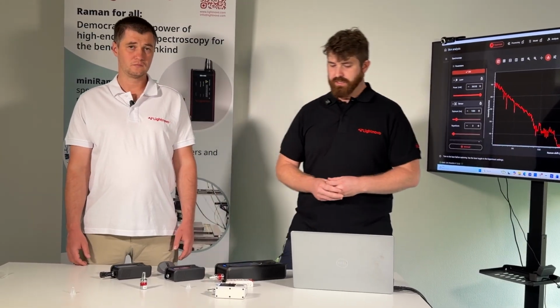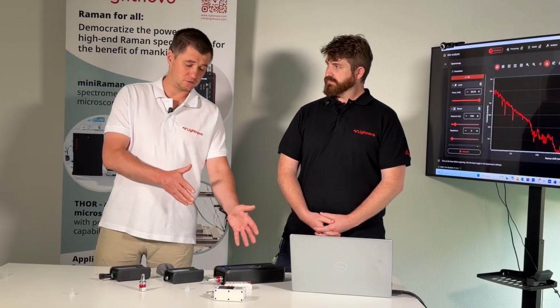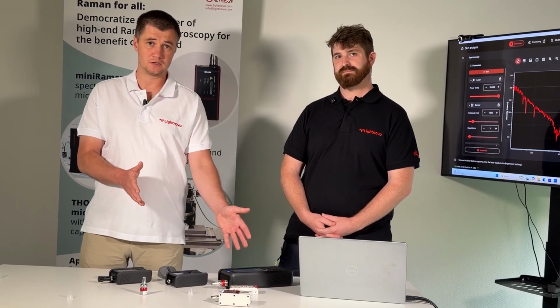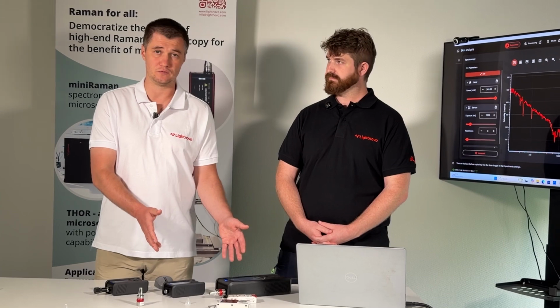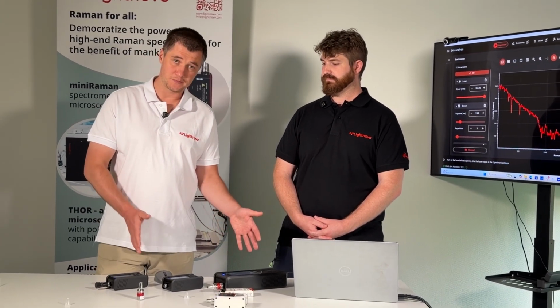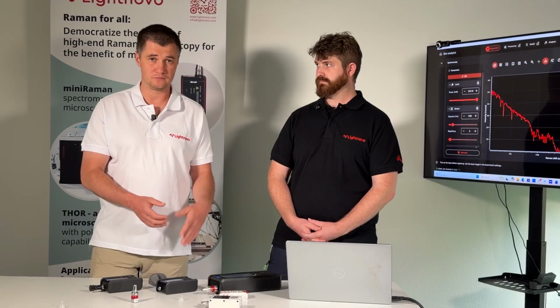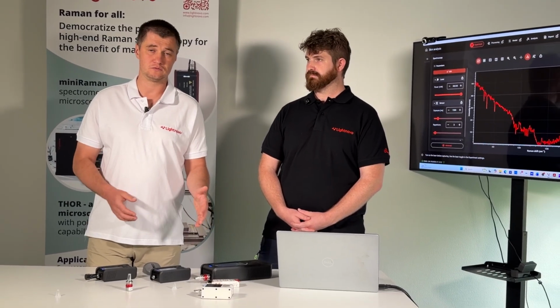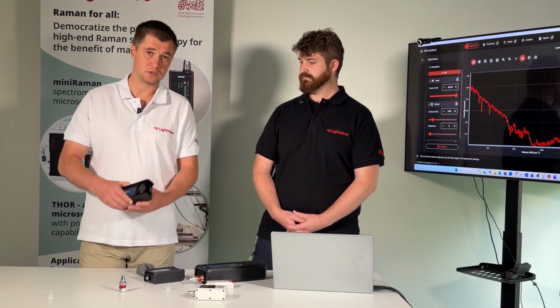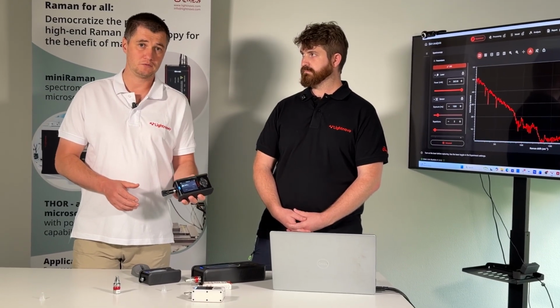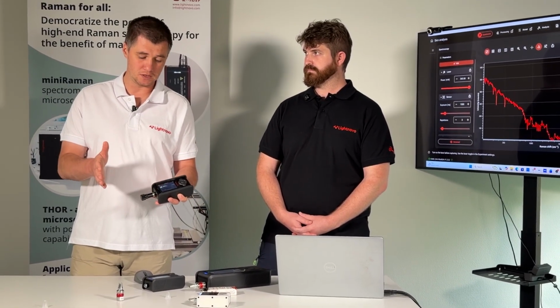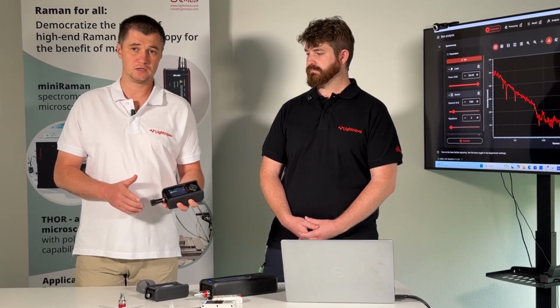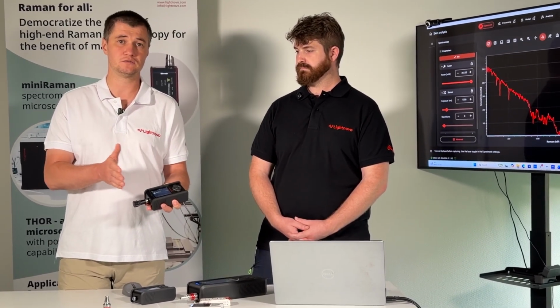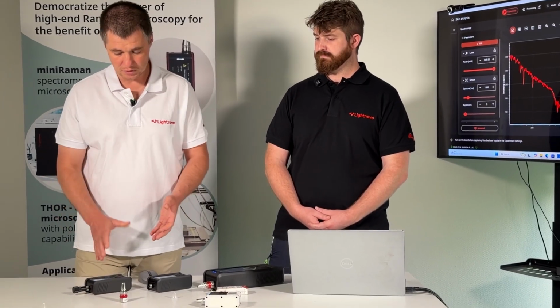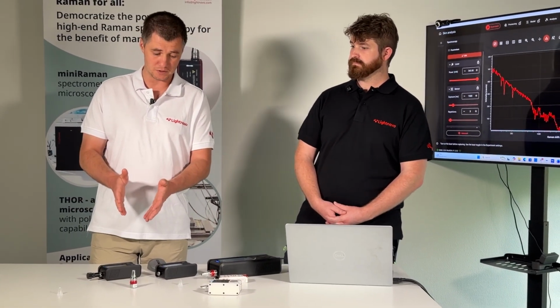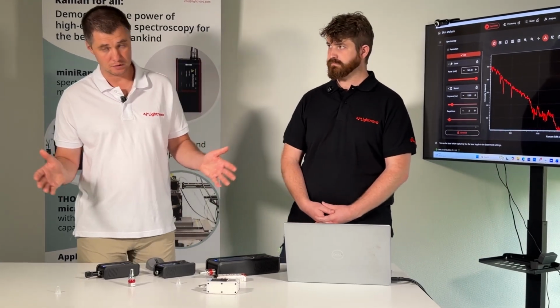hydration of skin. So, of course, as a general trend, 830 provides less fluorescence on average, and it's more suitable for more pigmented skin. However, spectral range is a little bit limited, so we start from, let's say, 100 inverse centimeters to 2500. But when it comes to 785, a very popular laser wavelength, you can also see CH with our device, so until, let's say, 3200 inverse centimeters, also starting from 100. A little bit higher sensitivity due to the wavelength, but a little bit more fluorescence on average compared to 830.